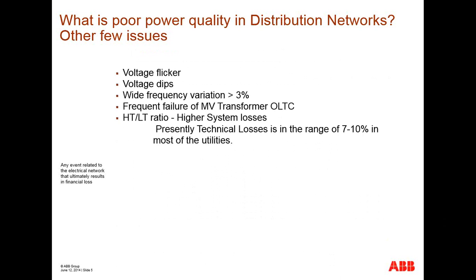If we look into the distribution utilities today, it is in the range of 7 to 10%. When you talk about the HV to 33 kV or 11 kV system, it is about 1.5% or 1.6%, and medium voltage to low voltage it is in the range of 2%, and below low voltage it is in the range of 4 to 6%. So it is obvious that we need to put the compensation at the distribution system as well, in order to minimize the technical losses.